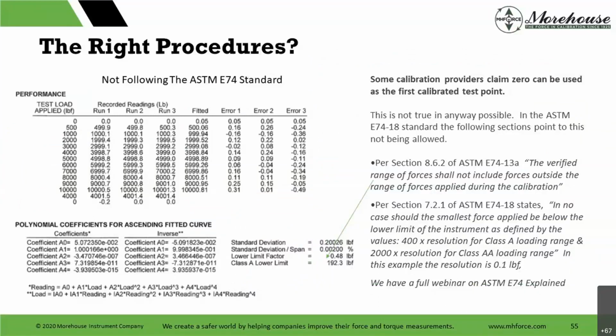But here, the E74 standard, the right procedures, basically says, hey, the verified range of forces shall not include forces outside the range of forces applied during calibration. And then we also have, in no case should the smallest force applied be below the lower force limit of the instrument as defined by 400 times the resolution for Class A verified range of force and 2,000 for Class AA.